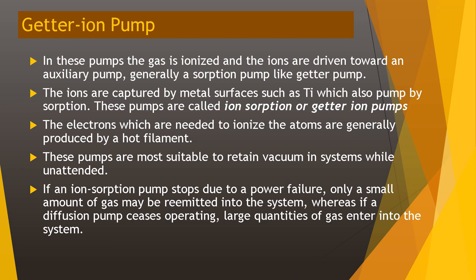The getter ion pump ionizes the gas and drives the ions toward an auxiliary getter pump, generally a sorption pump. The ions are captured by metal surfaces such as titanium, which also pump by sorption. These pumps are called ionsorption or getter ion pumps. The electrons needed to ionize the atoms are generally produced by a hot filament. These pumps are most suitable to retain vacuum in systems while unattended — if an ionsorption pump stops due to a power failure, only a small amount of gas may be re-emitted into the system, whereas if a diffusion pump ceases operating, large quantities of gas enter the system.